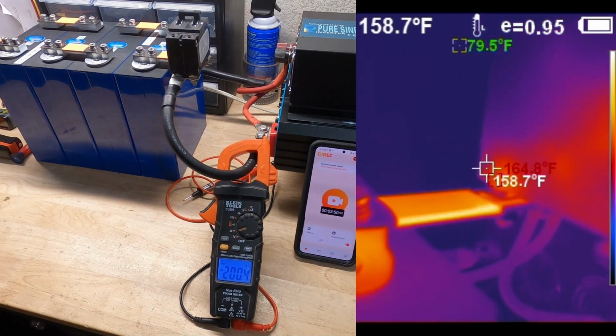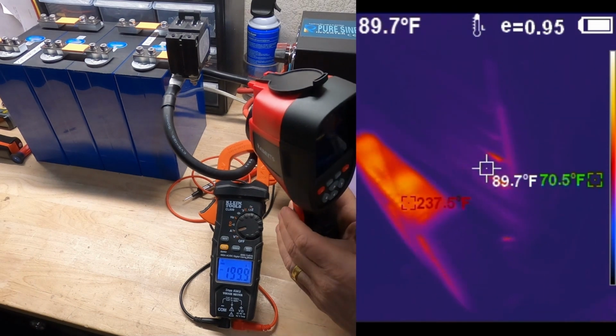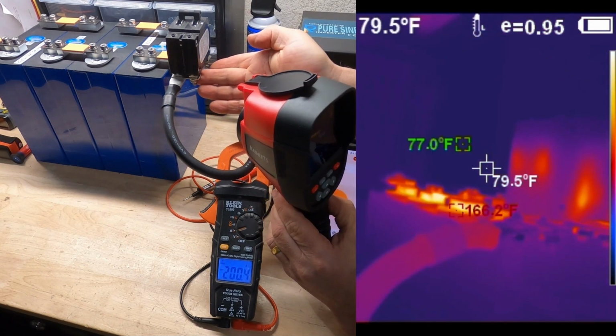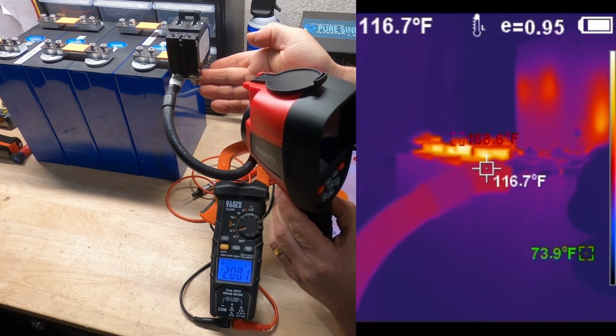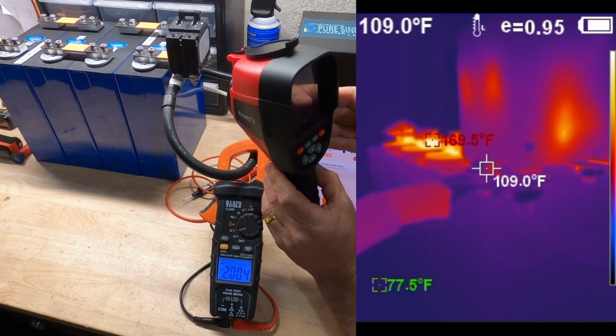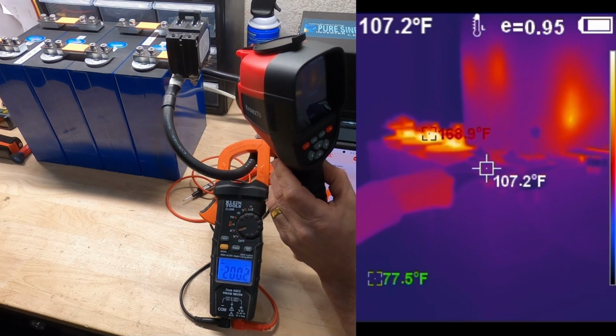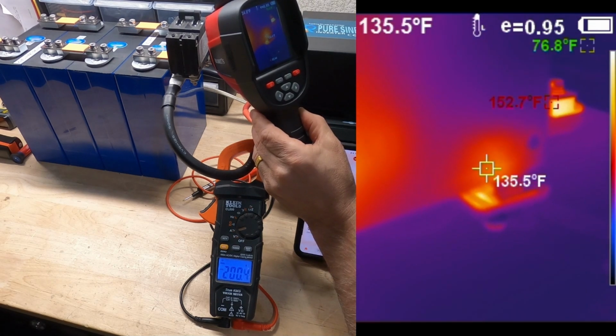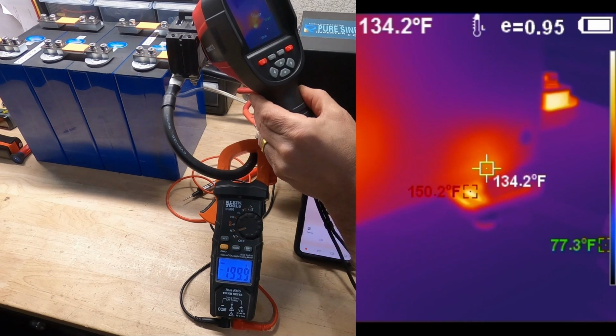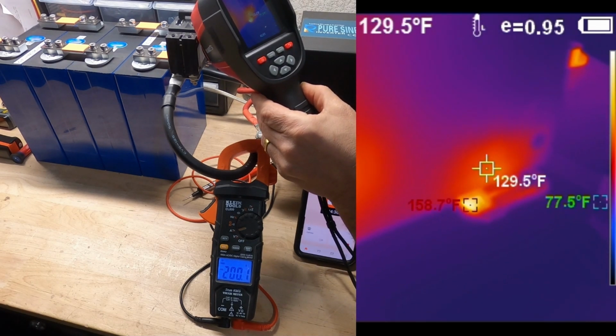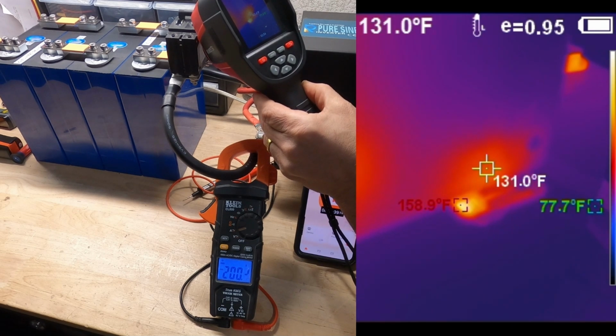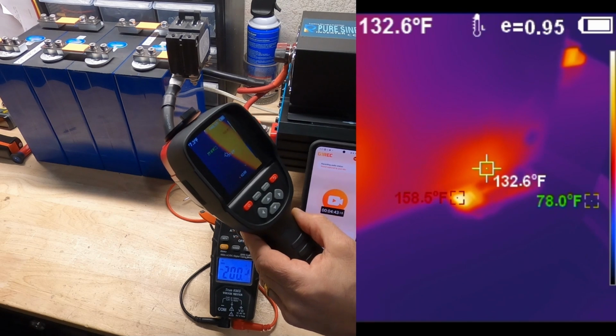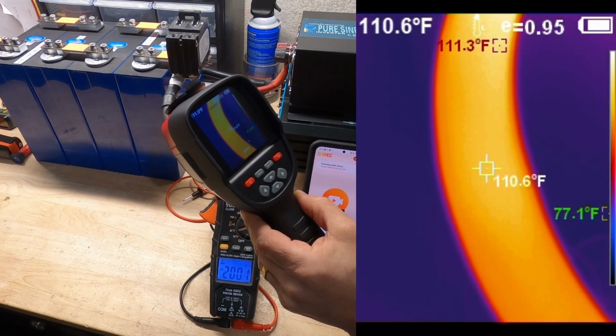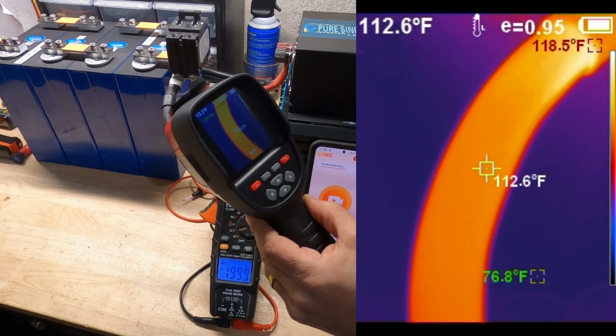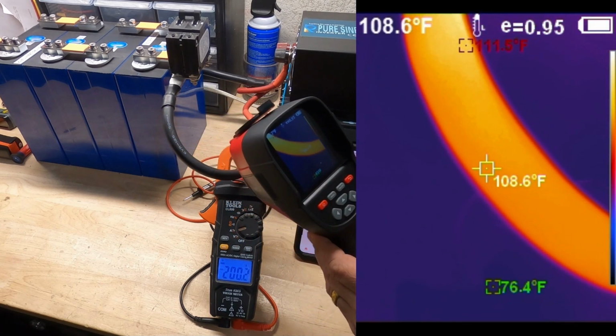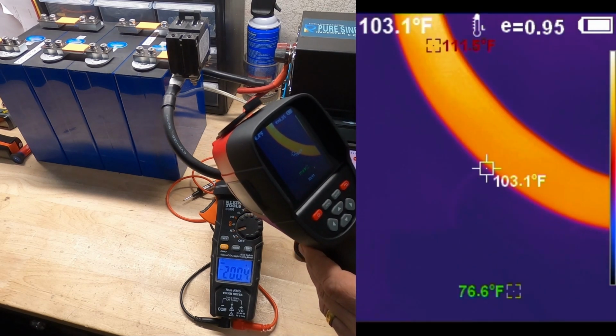I do not see a problem so far with the breaker or the cable. Contact terminal on the breaker about 110. The breaker itself internally 130. That's the hottest point right there, 132 degrees on the breaker itself. The cable's good. I do not see a problem with this cable at all. I'm still pushing 200 amps. It's been about 5 minutes.